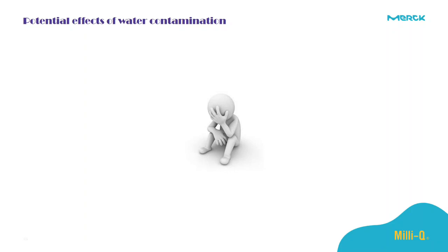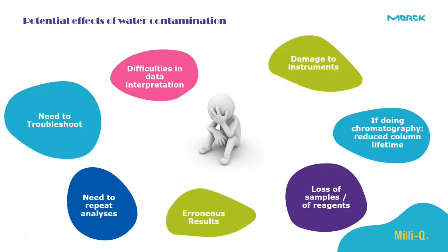And now in the next few slides, we will see together the effect of water contaminants on the instruments, on the results, and on the application. So let's see what effects water contaminants can have in your lab. First of all, they can damage your instrument for sure. And if you are doing chromatography, it will reduce the lifetime of the column and extra cost will be added. Also, it may lead to loss of sample and reagent and erroneous results, and you may need to repeat the analysis and troubleshoot, and you will face difficulties in data interpretation.